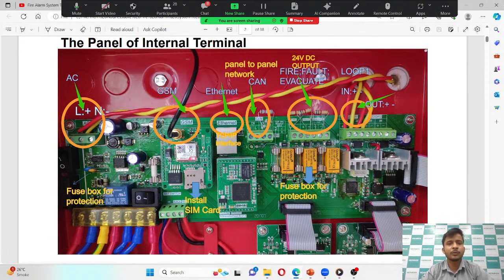This is the motherboard of our fire alarm main panel. As you see, we have all the components on it. For termination of the AC power, you need to connect the line, neutral and earth wires there. Then we have a GSM module for connecting the SIM card, to send a message to the monitoring person or the security person in case of fire. Then we have an Ethernet port for connecting our panel with the software. Then we have the CAN bus for connecting multiple panels in the same network.